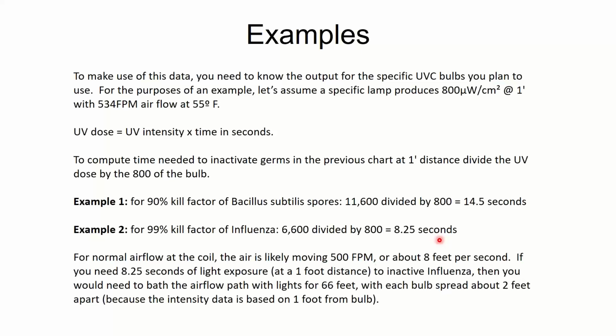I'm usually at 500 feet per minute where these bulbs are installed, typically the evaporator coil area. If I go further down the duct, the dimension is smaller so velocity would be more, making it even worse. The coil is where the air is slowest, so that's my best chance of killing it because I'll be near the bulb longer.